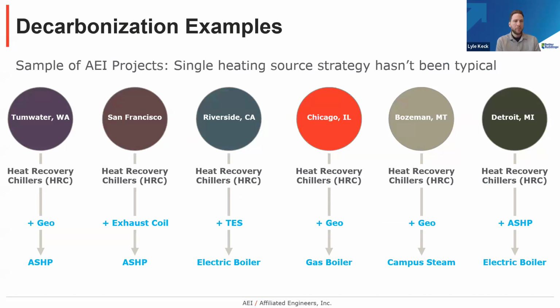So I wanted to illustrate it. Here's a sample of projects in different climate zones, largely across the West and Midwest in this case. You can see that the base technology for this is heat recovery chillers throughout, or some type of water-to-water heat pump that produces heating and cooling simultaneously. Below that, in blue, you'll start to see a mix of right-applied technologies. These are super efficient technologies, but they might come with some cost constraints or some technical limitations. And so these are your workhorses that are right-applied in the middle. You see a mix of geothermal heating and cooling, some thermal energy storage, or maybe even using the building exhaust air as a source of heat pump heating and cooling.